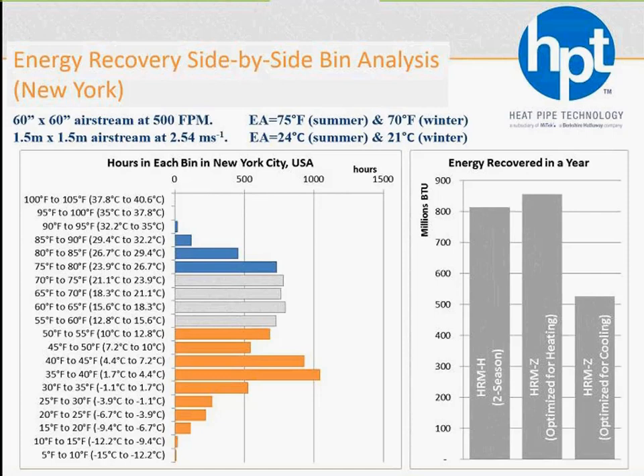Okay, good question. We get this asked all the time for this particular product, and some of our products with higher circuit capacities, that tend to be the DHPV, the vertical tubes, and we'll be talking about the split passive shortly. We leave it to the design engineers to basically observe local codes and do the monitoring if required, if it exceeds a certain amount. But for the bulk of our products, circuits are numerous, including the product I've just shown you here, the HRM heat recovery module and the standard wraparound heat pipe. The circuits are numerous, and the amount of refrigerant is not that huge. I mean, you're talking in terms of ounces, a pound or two max, without revealing too much about our charge here. So for some products, it's small and you do not need monitoring; for other products, you may want to consult local codes and standards to make sure, if an amount is exceeded, you may need to do some monitoring. So I hope that answers that question.